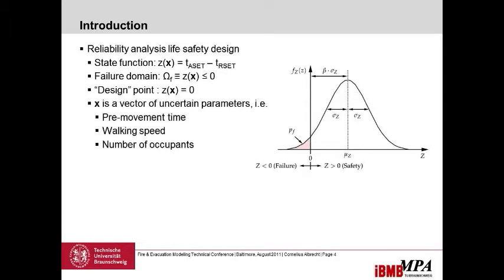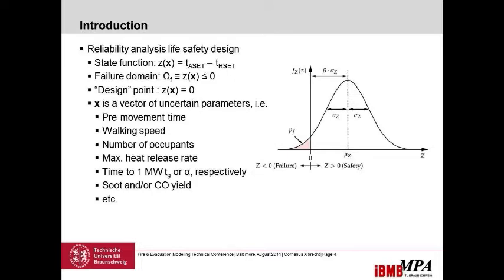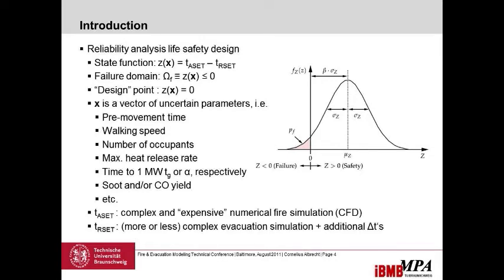In this state function, x is a vector of uncertain parameters. On the evacuation side, that might be pre-movement time, walking speed, or number of occupants. On the fire side, I might have the maximum heat release rate, the fire growth parameter — for example, the time to one megawatt or the alpha parameter — and yields such as the soot yield, carbon monoxide yield, et cetera. To compute the available safe egress time, we use numerically expensive tools like computational fluid dynamics.